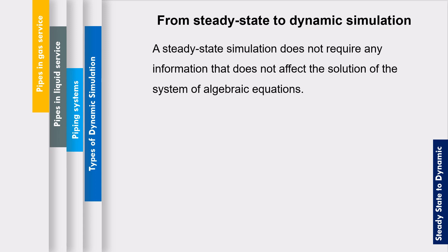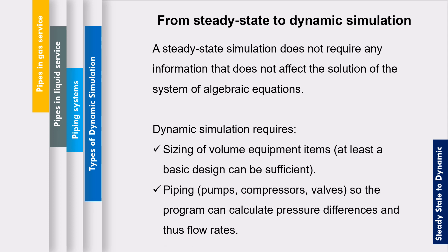Steady state simulation does not require any extra information about the system. We do not need to know the proper system design, sizing, or anything else — we just need to solve the basic algebraic or thermodynamic equations. But what we normally do is simulate something at steady state on HYSYS and then convert it into a dynamic system. If we are converting a steady state system to a dynamic system, we need to know the sizing of volume equipment items, meaning the volume holdups in the system.